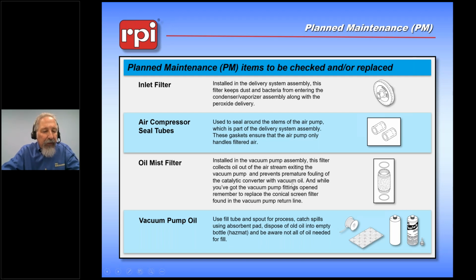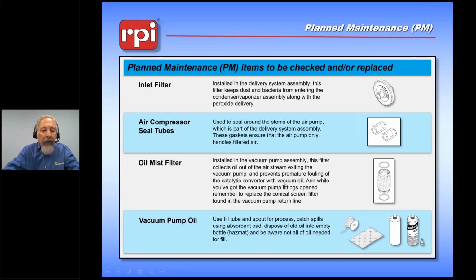These vacuum pumps that are used in hydrogen peroxide sterilizers will generate an oil mist along with the outflowing air. We need to condense that mist and return it back to the pump so it can use it as oil. We give you the amount of vacuum pump oil that you will need. We give a way to manipulate the oil and an empty bottle so that you can take the oil that's been used within the system successfully and treat it properly.